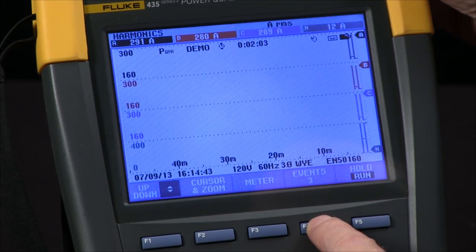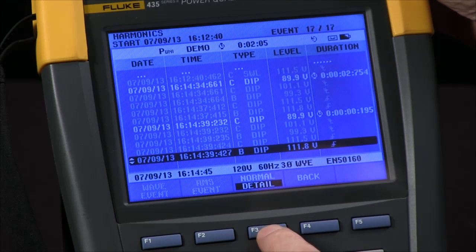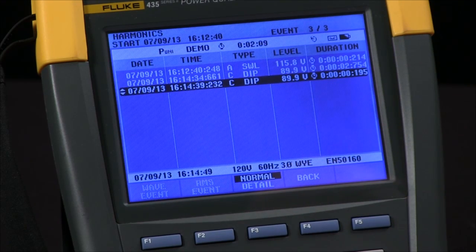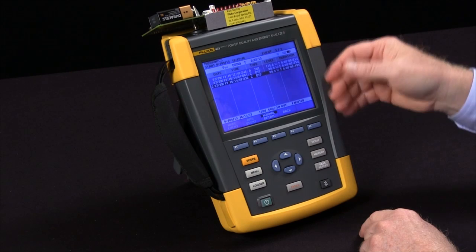If I hit the events key and come to see normal, you'll see I had a few dips and swells occur during the test. So even during harmonics testing, I see other types of voltage events.